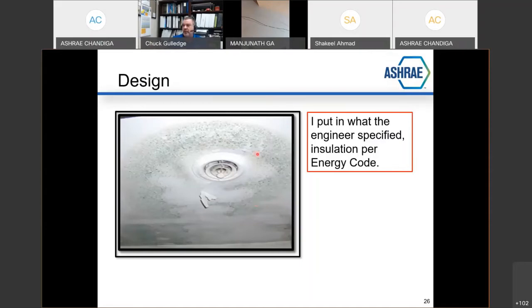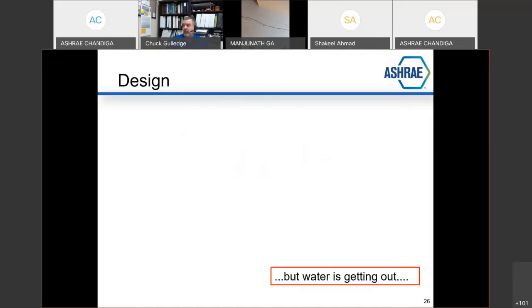And sure enough, behind a hard ceiling, minimum insulation was put on supply duct that was putting out 55 degree air through the transport path. And it was all raining behind the ceiling. And you can start to see the mold that was starting to grow, all because somebody followed code and didn't do the engineering that should have been applied.